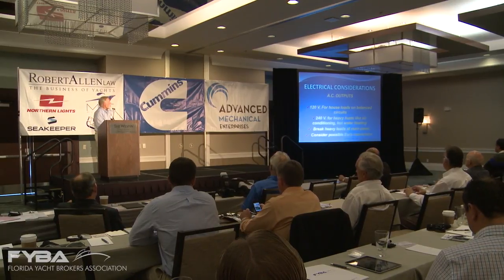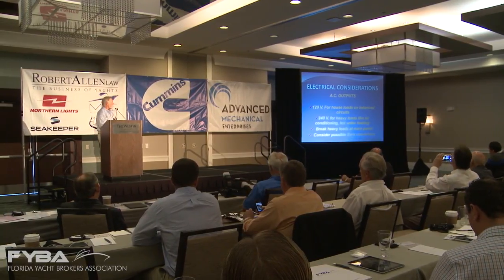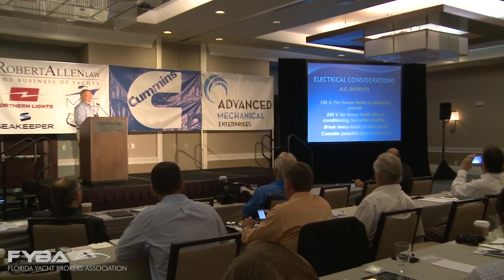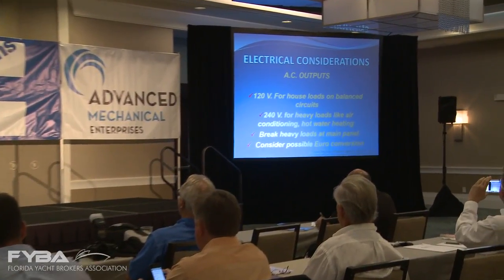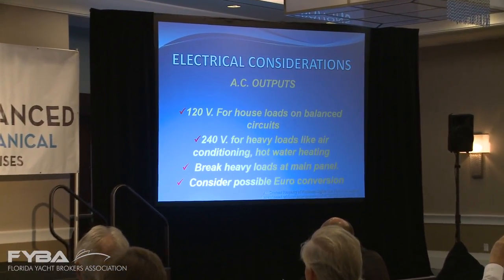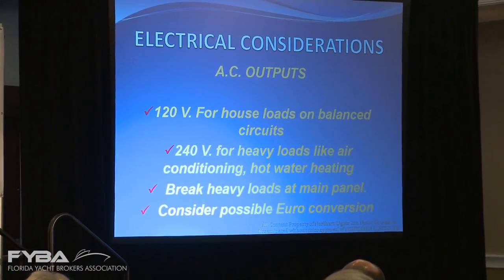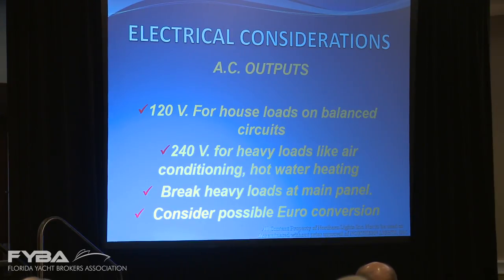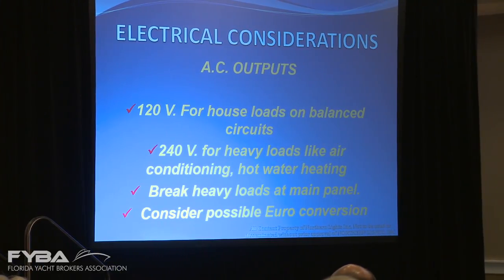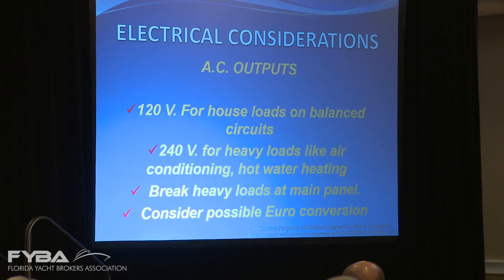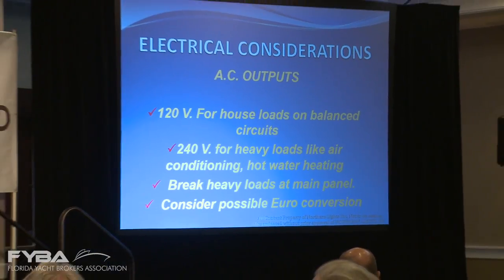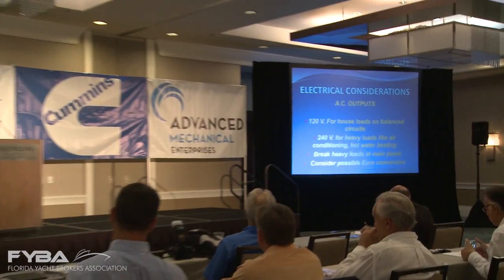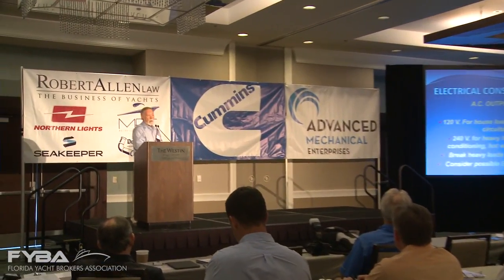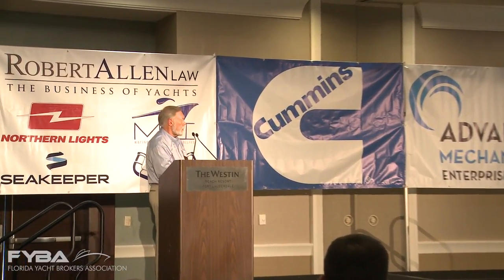Okay, from the electrical side, we're concerned about the AC outputs. If you're involved in the planning stages of a new build, this is a terrific place for you to be able to do the customer some big favors. Generators can be designed, and most generators are designed, to supply two voltages, a high and a low voltage, typically 120 and 240. The 120 volt current is typically used for house loads or what we call hotel loads, relatively light loads like lighting and entertainment systems and so forth, but not really heavy current draws. So 120 volt is ideal for those.